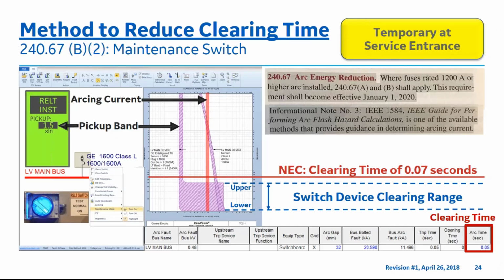Again, this 1.5 pickup band temporarily lowers the arc flash energy during an arcing current fault event on the load side of the low voltage power distribution section. To be clear, this maintenance mode feature is not intended for permanent use, as coordination and selective coordination will be compromised if there is a downstream fault that could lead to a power disruption.